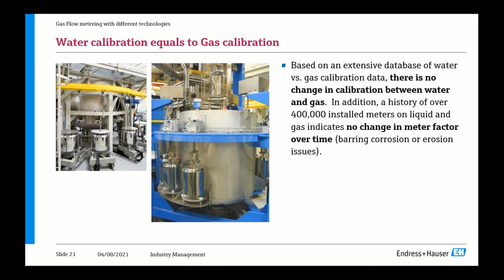An alternative to this proving methodology is to use a Coriolis meter as a master meter as well. Same thing: by establishing the traceability between water and gas measurement on the meter, it can be used to prove other meters of any type. Next slide, please.